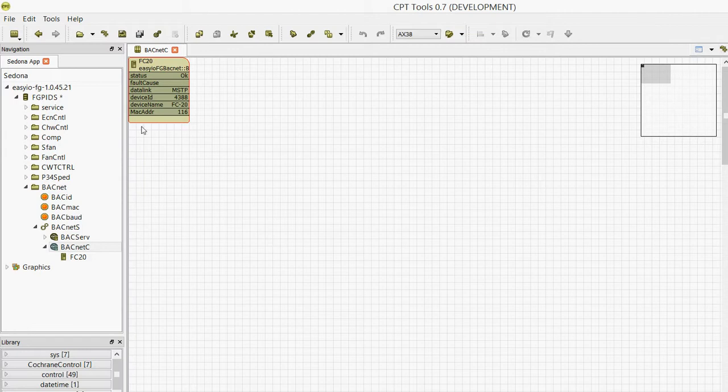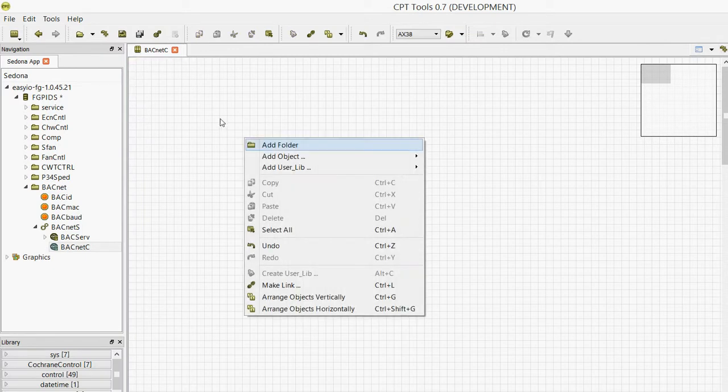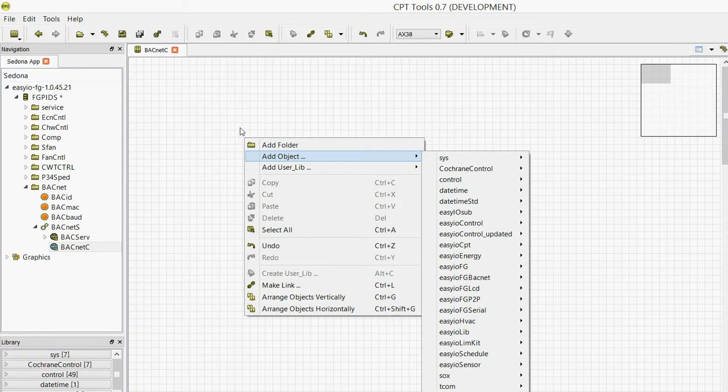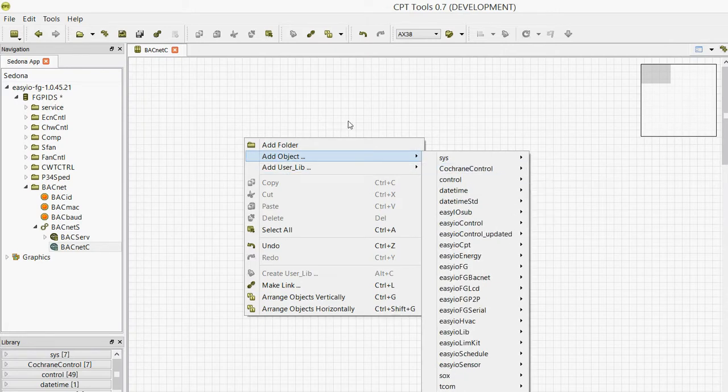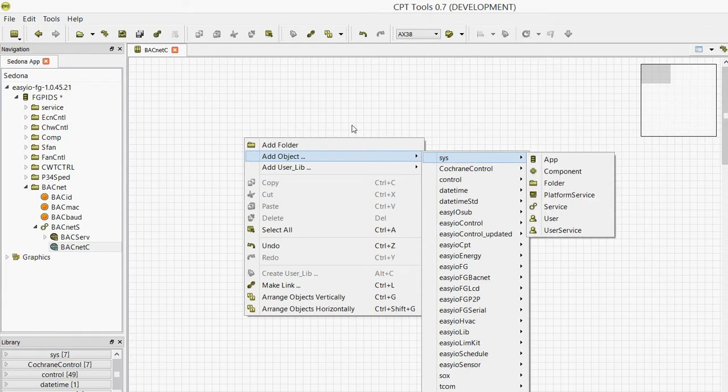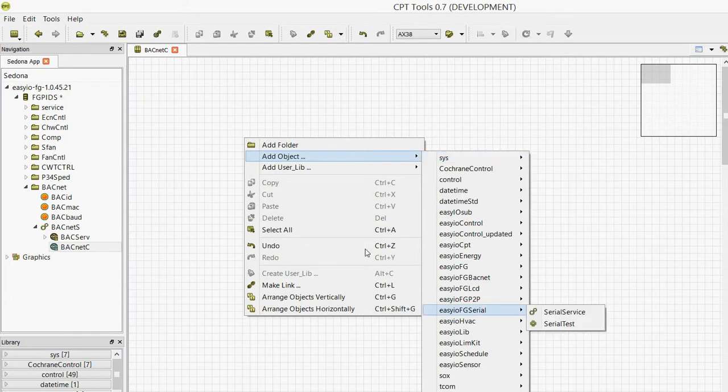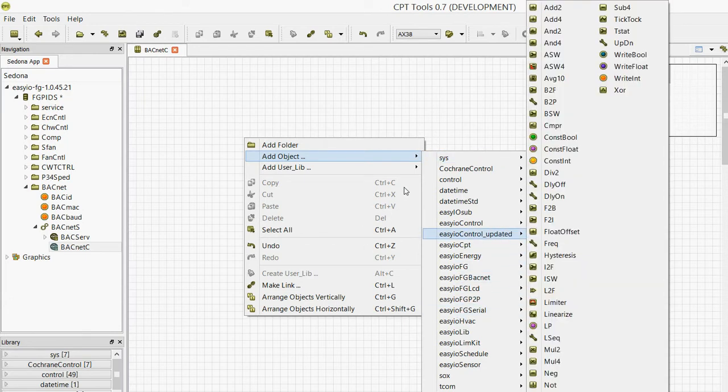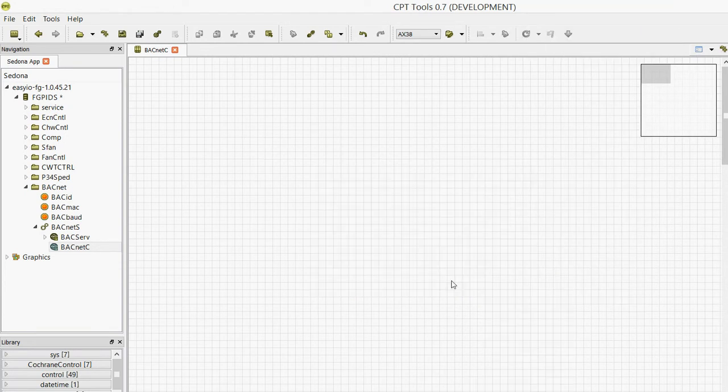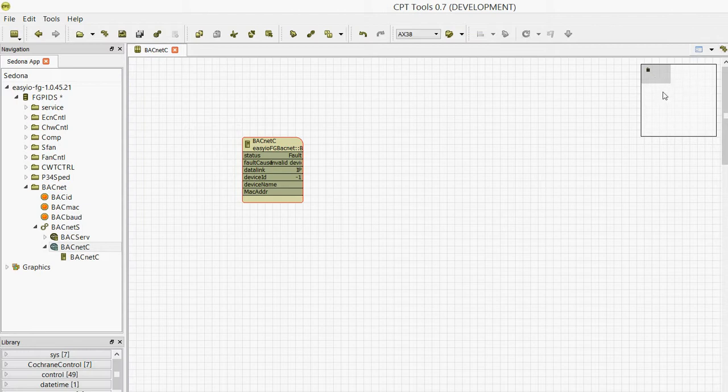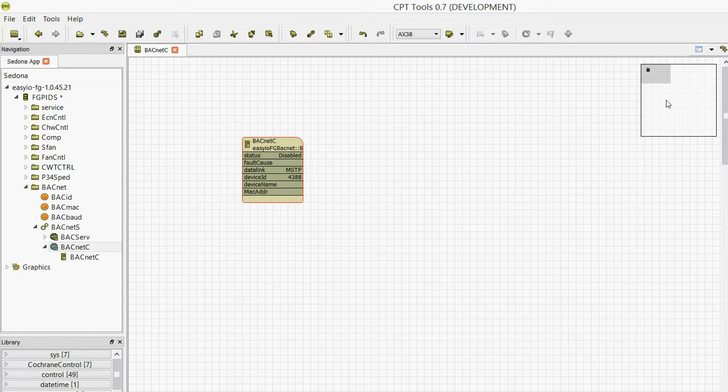Now the other way I could have done that was to delete that and just manually add it without doing a discovery. If you've got a number of VAVs and you know what they are, you could actually save them and just manually add them in as client devices. If you go to BACnet here and edit a client device, obviously it doesn't tell you anything there. All you actually need to know is that it is an MSTP device, device ID 4388, and just enable it and wait for it to come live. So if we just watch that, there it is.